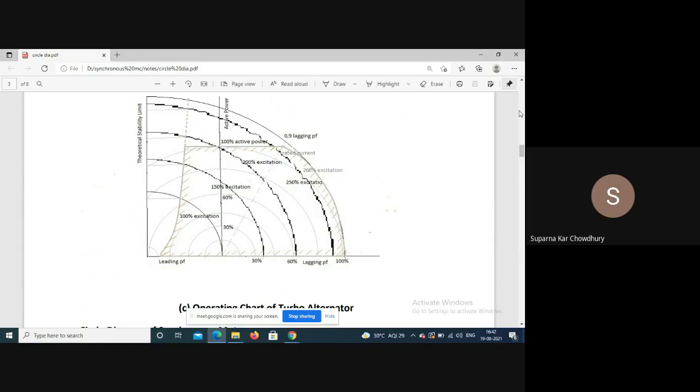100% excitation means Ef equals rated voltage Vt. So 260% excitation means the field excitation is such that the induced EMF is 2.6 times Vt, and the field system must be designed accordingly. To define the safe operating area, first consider the active power output along the voltage phasor line.